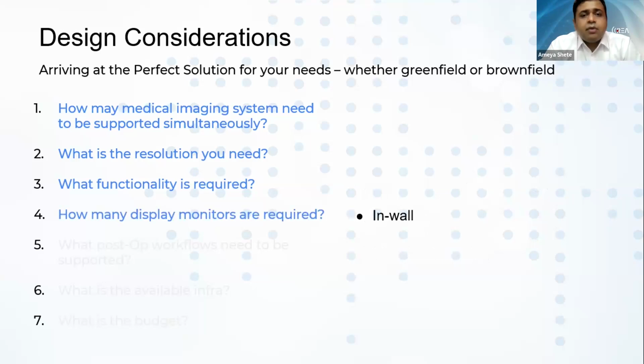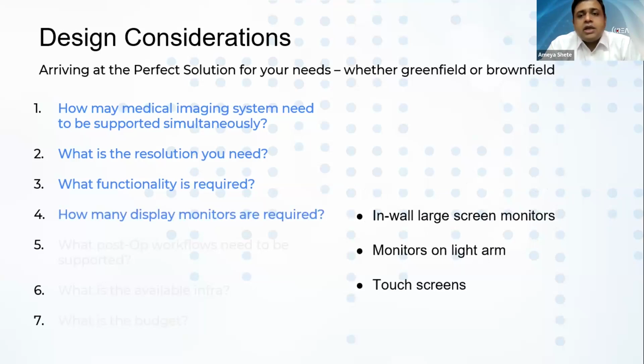Next is how many display monitors are required. Whether you want in-wall large screen monitors which are flushed in the wall itself. Do you need monitors on the light arm, touchscreen panels, and whether the system should be medical grade or non-medical grade. Whenever you have monitors which are outside the surgical field, you may do with a non-medical grade or a commercial grade monitor as well. Whereas when it comes to the surgical field, it has to be a medical grade monitor.